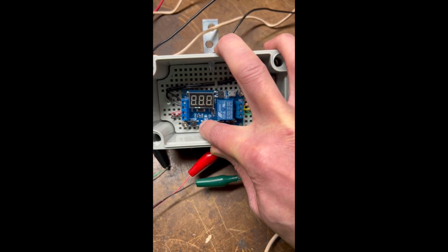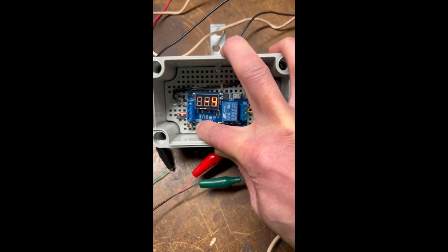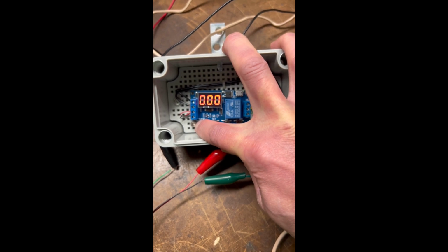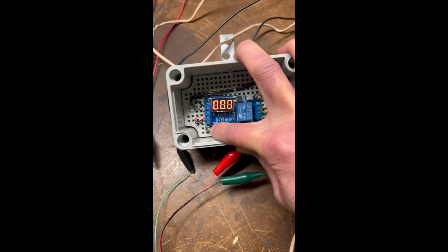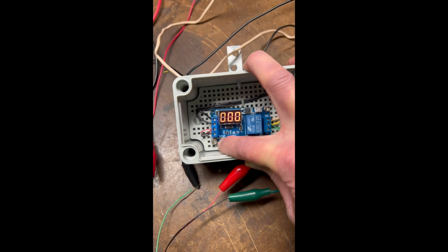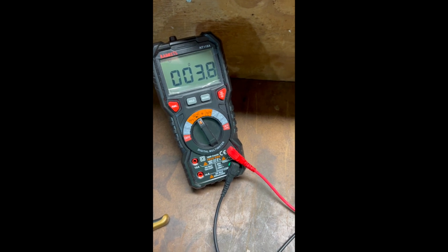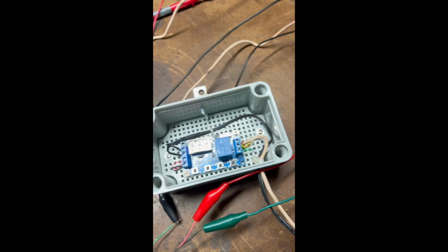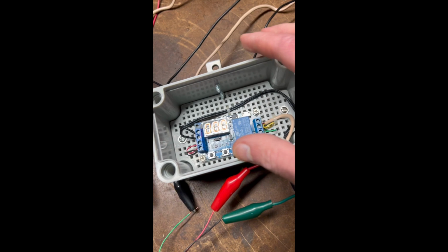And then I'm going to press and hold the set button, or P4. I'm going to press the stop button. And now we're back to this mode. So right now, if we turn our ohm meter on, we'll see we are shorted. So we are in a closed and alarm position at this point.